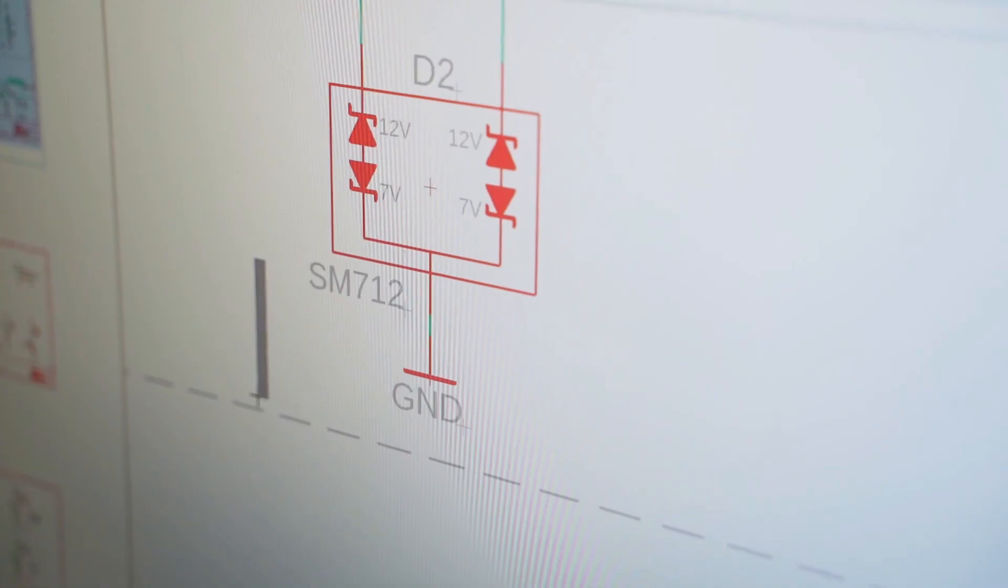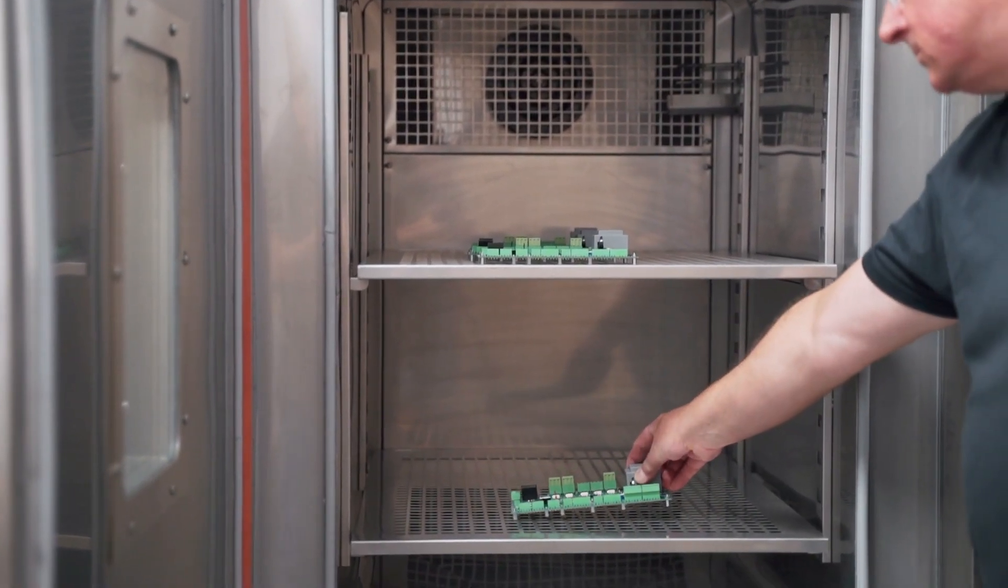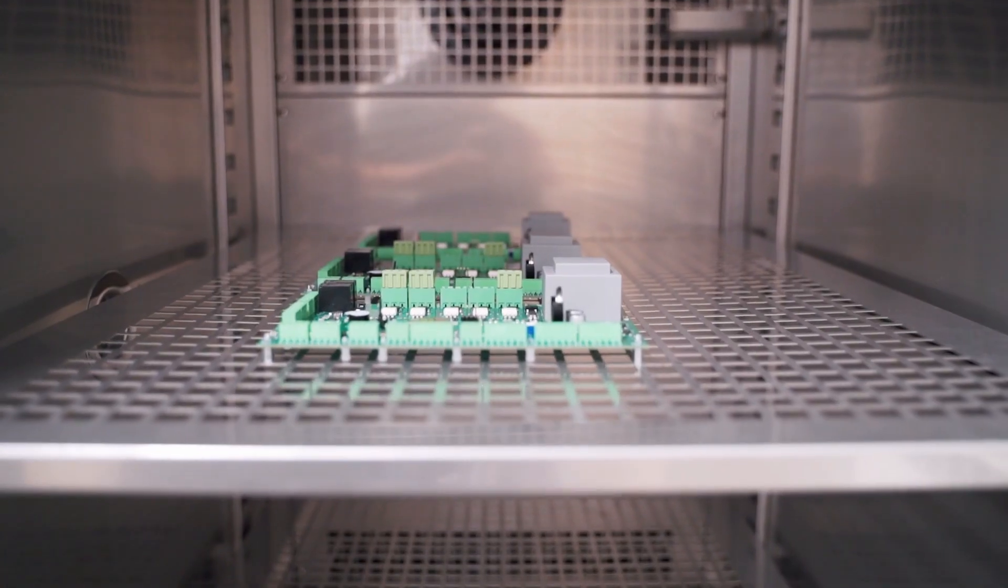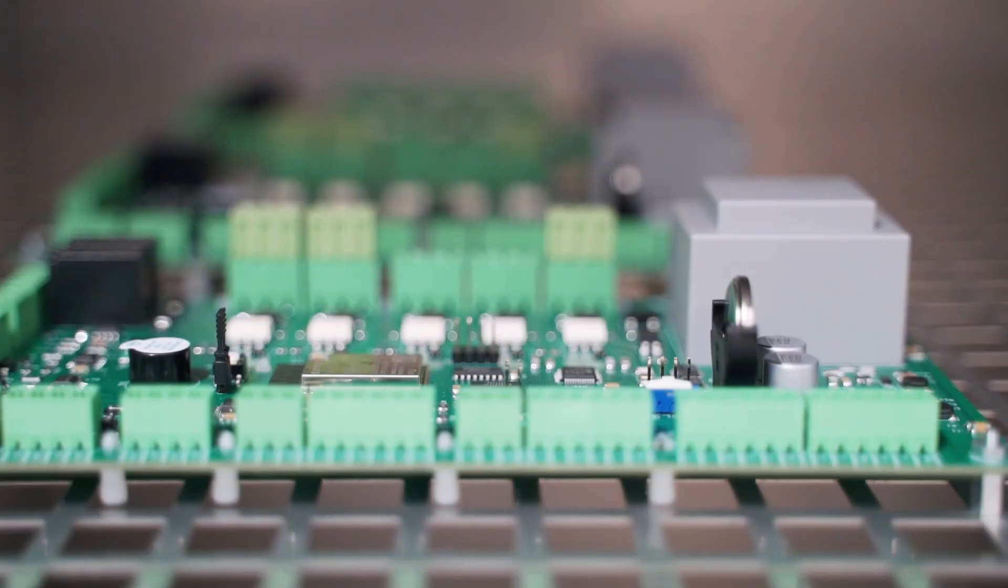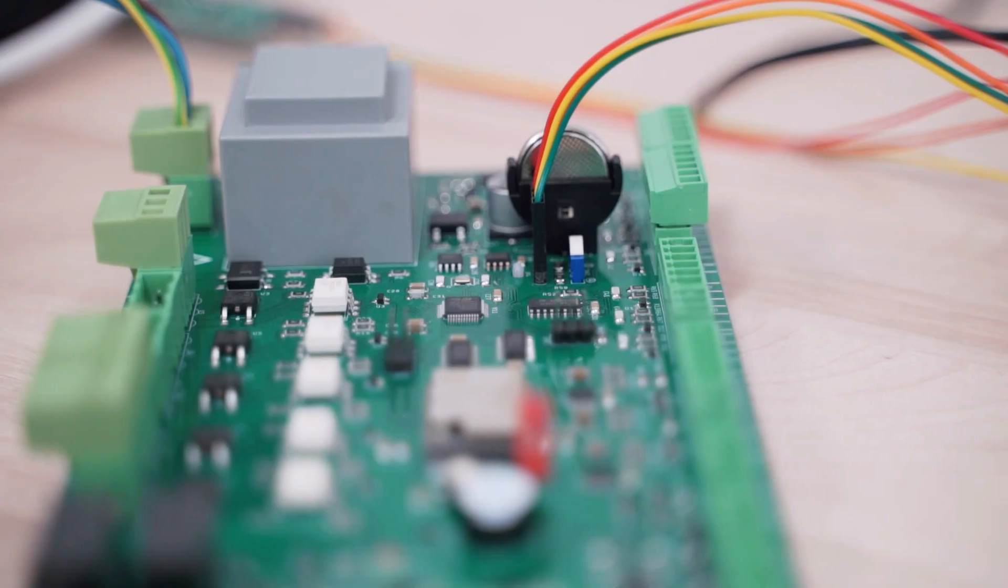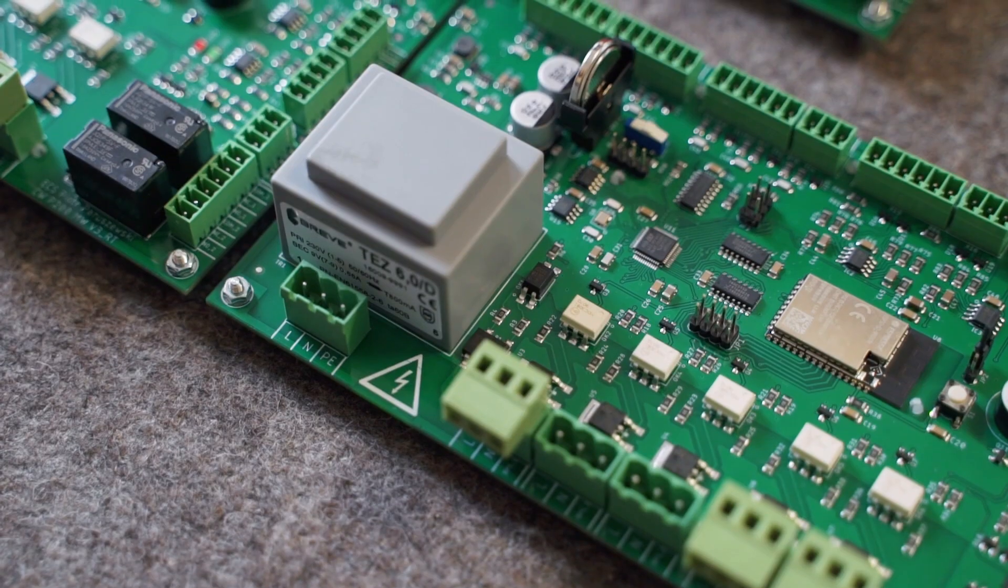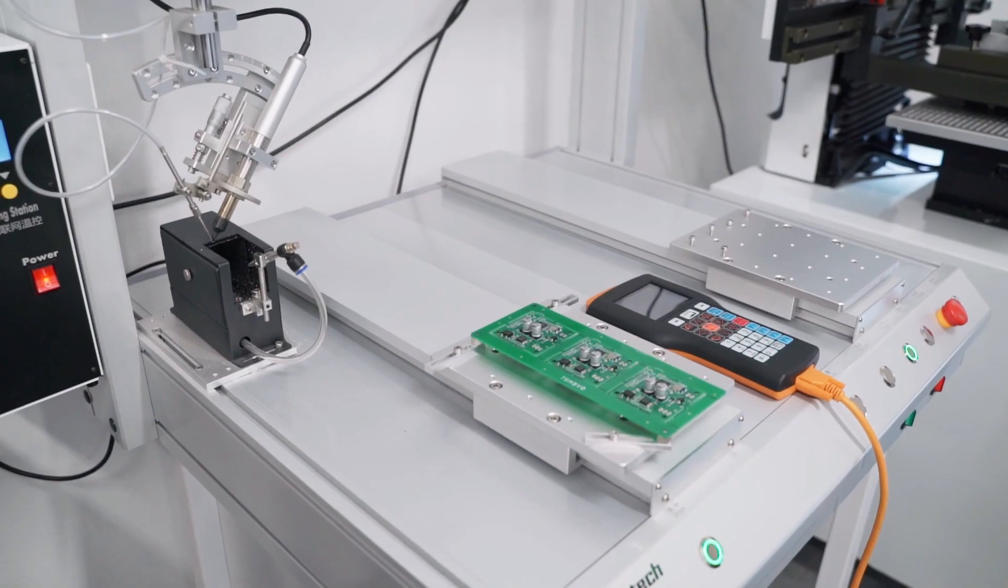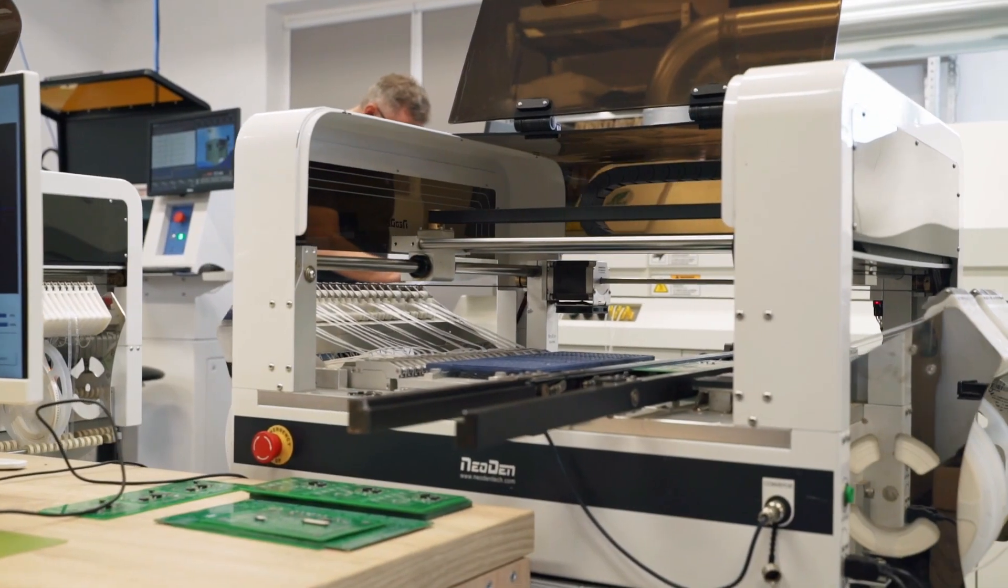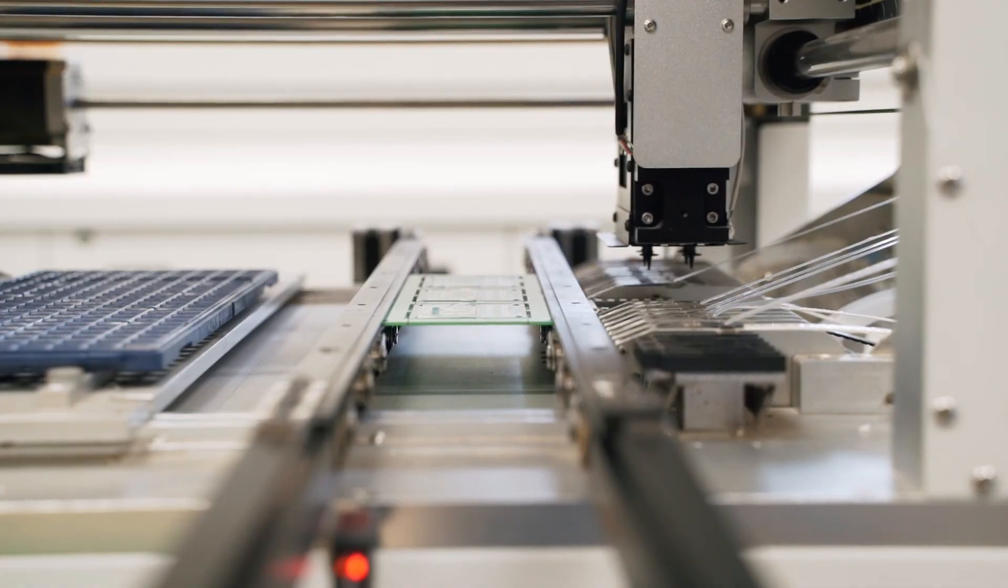It is then tested in a climatic chamber where it stays for about a month and is subjected to cycles of variable temperature, from plus 80 to minus 40 degrees Celsius. In this way, it is possible to simulate about 30 years of recuperator operation and check how it will behave in various weather conditions. After testing and approval by an independent laboratory, serial production can begin.